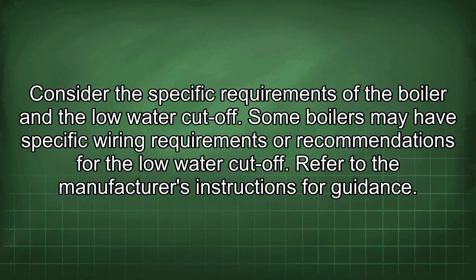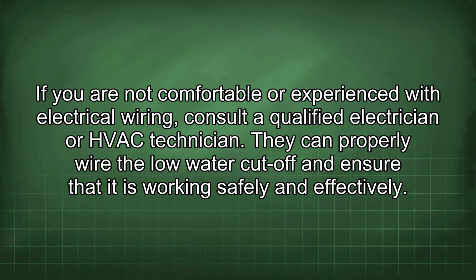Consider the specific requirements of the boiler and the low water cutoff. Some boilers may have specific wiring requirements or recommendations for the low water cutoff. Refer to the manufacturer's instructions for guidance. If you are not comfortable or experienced with electrical wiring, consult a qualified electrician or HVAC technician. They can properly wire the low water cutoff and ensure that it is working safely and effectively.